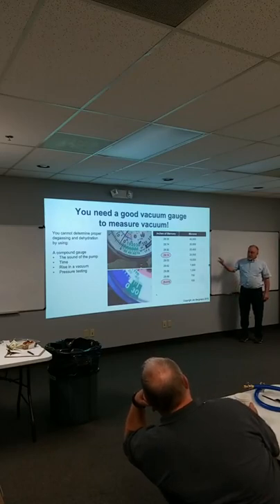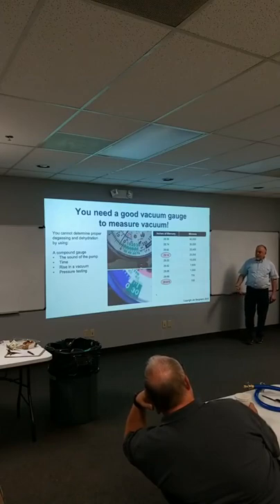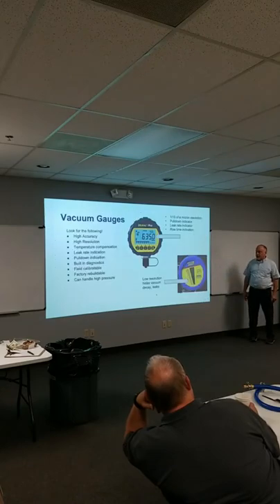Back in the day, right? In fact, I remember when I was talking to guys at EMS, that was a big thing. If you don't have a vacuum gauge, how can you tell when the pump's got a deep enough vacuum? Sound of the pump, that was a big thing. Remember? It came out of a textbook, I can't remember which one. Yeah, it was the one right after they forgot everything you knew about vacuum. Right? And honestly, God, I've seen more bad stuff in textbooks, so you can't rely on a textbook. The sound of the pump won't tell you the difference between 20,000 and 100 microns either.